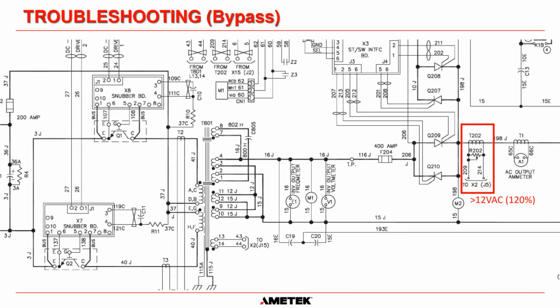And then the other thing that would transfer the system to bypass is we have a CT on the output of the system. This is the CT here, and it has a circuit on it that converts the CT voltage through a burden resistor into a signal. It's a 10 volt signal for full load. So if it's a 10 kVA system, full load is usually 83.3 amps, something like that. So if you had 83.3 amps flowing through T202, you would measure 10 volts going to the control board. If it goes above 12 volts, in other words, we go above 120% of the rated load of the system, then the system will transfer to bypass if bypass is available.